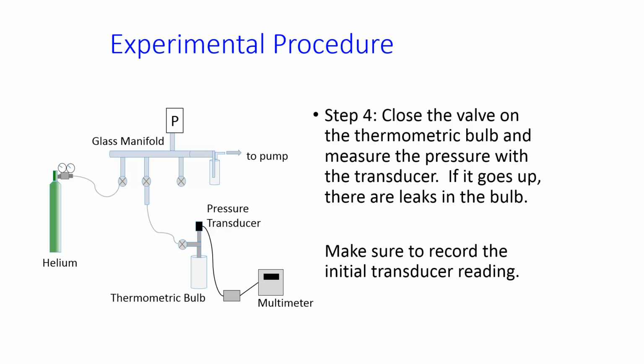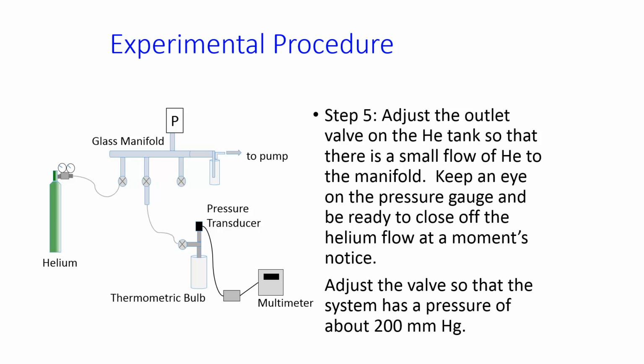When the system is pumped out, you need to close the valve between the thermometric bulb and the manifold and watch the value on the pressure transducer. If the voltage starts changing, this implies that there's a leak somewhere in your thermometric bulb system, which you need to fix before you move on. Your TA can help you with that.